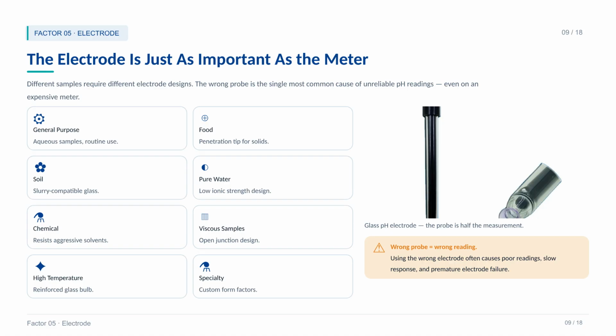Factor 5, and this is the one most people underestimate, choosing the right electrode. The electrode is just as important as the meter. I'll say that again. A $1,000 meter with the wrong probe gives you $1,000 garbage. There is no one-size-fits-all electrode. General purpose, food, soil, pure water, chemical, viscous samples, high temperature, every sample type has a matching electrode design. Get this wrong, and nothing else on the spec sheet will save you.